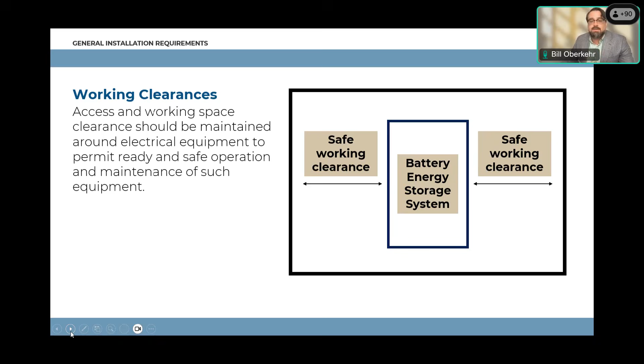Energy storage, we're in fire resistant separation now, so we're looking at primarily indoor. So if an energy storage system is inside a room or area that is indoors, that room or area shall have a minimum 2 hour fire resistance rating on all sides. That includes the ceiling of the room. That is something that comes up a lot to the clean energy siting team and our experts. Yes, if there is a room or area with an energy storage system in it indoors, the ceiling also needs to have that 2 hour fire resistance rating. Next slide, please.